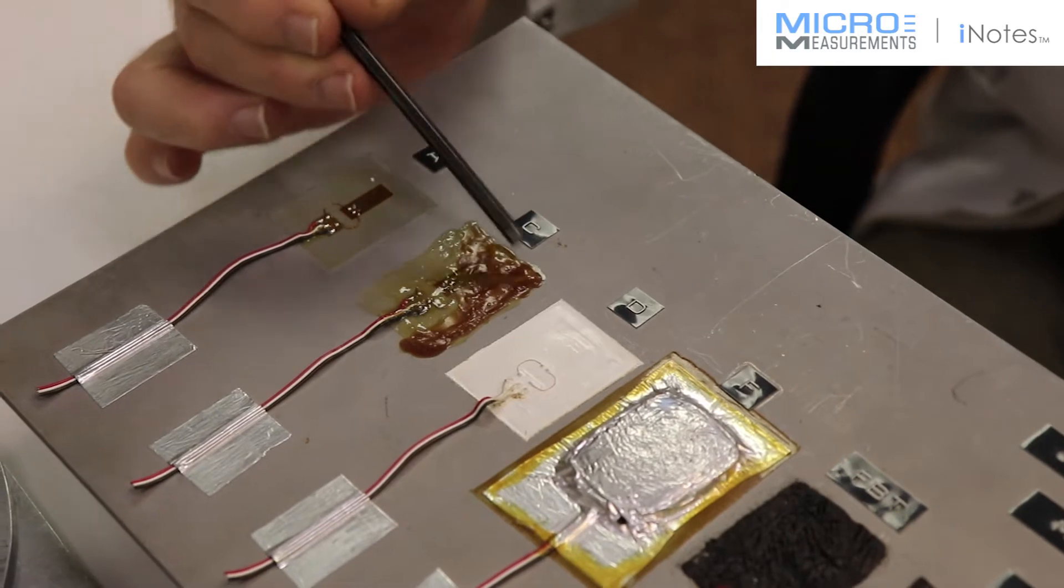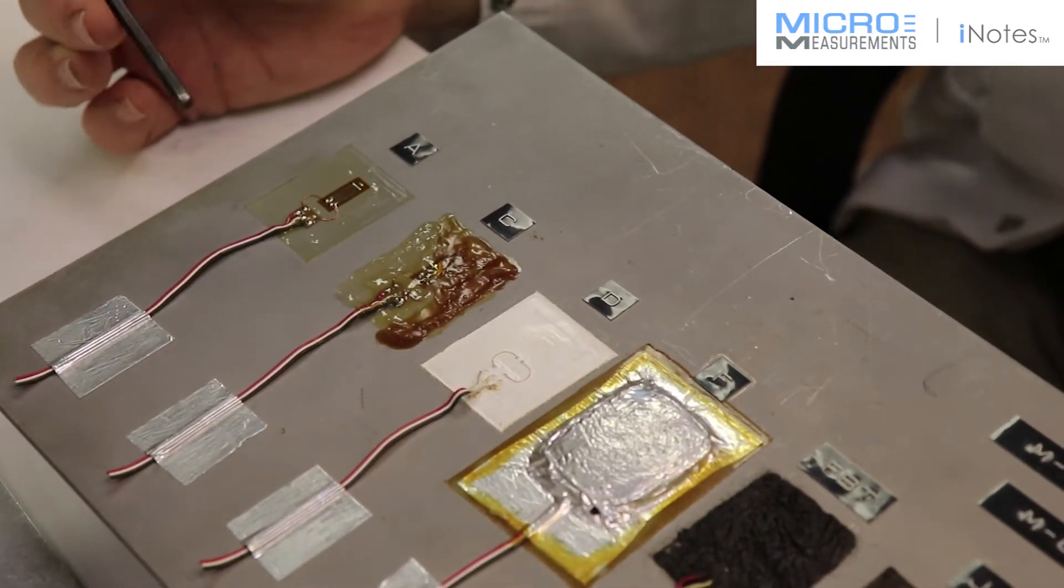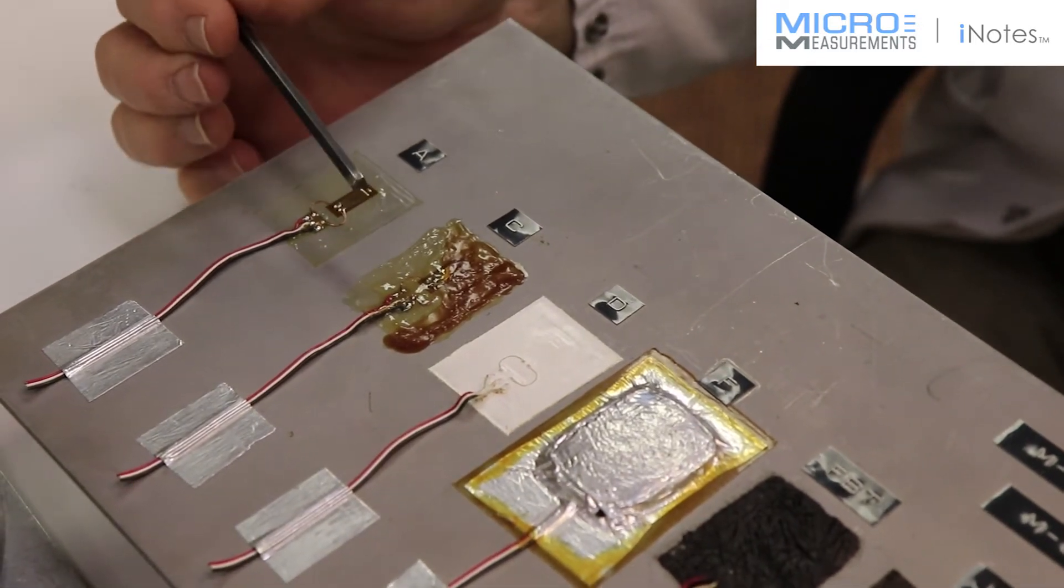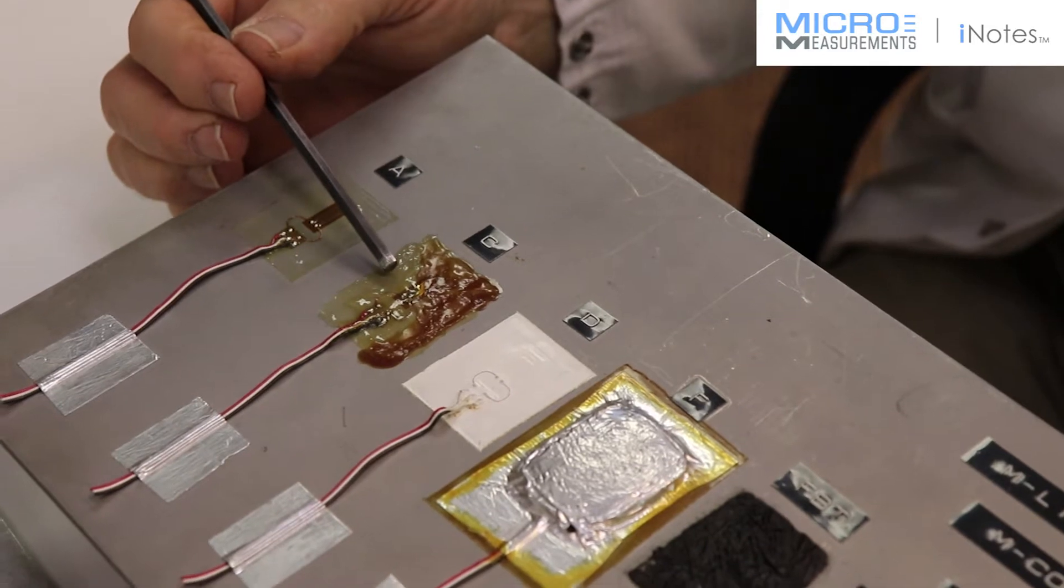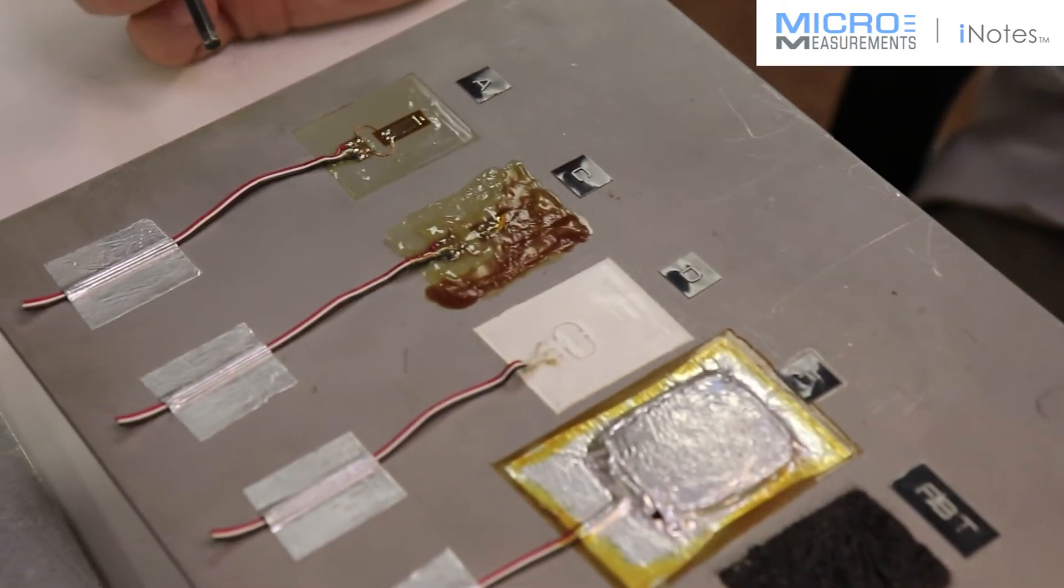Now if you look carefully you'll see there's M-Coat B over half of it. A lot of times you'll use the M-Coat B, the nitrile rubber material, as a vapor barrier. The RTVs use moisture in the air to cure them and so they will absorb moisture with time. So having the M-Coat B over the top of it makes it a better vapor barrier.